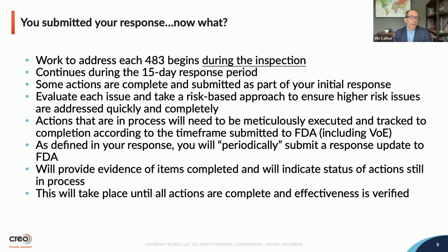And so a lot of warning letters actually lead to companies not doing this, right? So this is the number one way to avoid a warning letter, is to get into a periodic cadence of submitting your responses to FDA and making sure that those responses include evidence of completion of the actions.